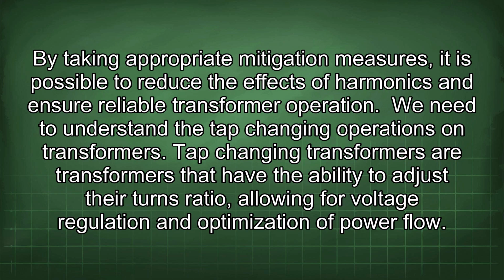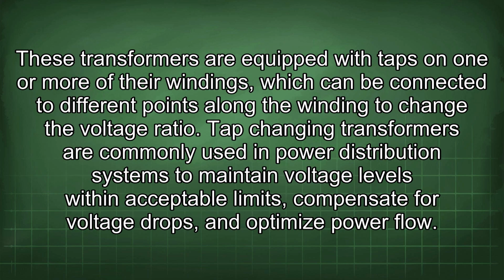We need to understand the tap-changing operations on transformers. Tap-changing transformers are transformers that have the ability to adjust their turns ratio, allowing for voltage regulation and optimization of power flow. These transformers are equipped with taps on one or more of their windings, which can be connected to different points along the winding to change the voltage ratio.